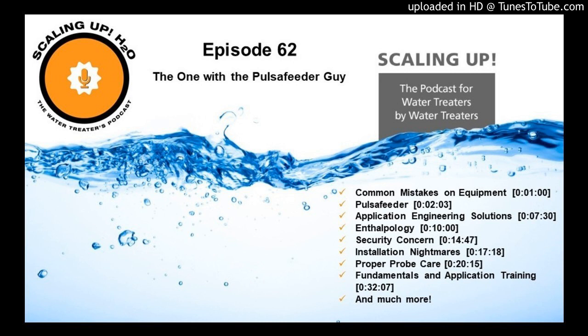So probably the most important measurement to sense, specifically in evaporative coolers or even boilers, is conductivity. pH and ORP are selectively used, but controlling conductivity is key. So I just emphasize, make sure you've got a good conductivity probe. Make sure you're maintaining it correctly. I strongly recommend a toroidal style conductivity probe.